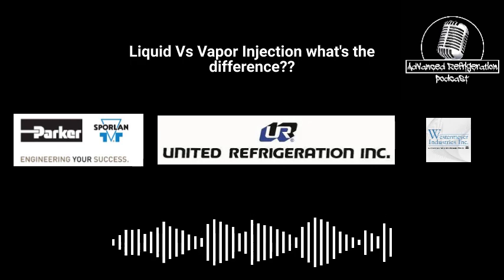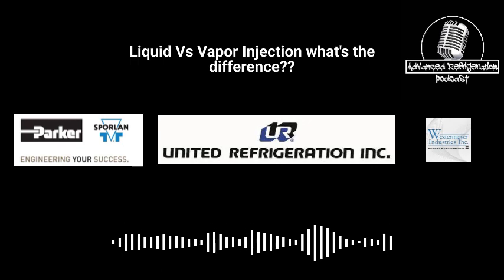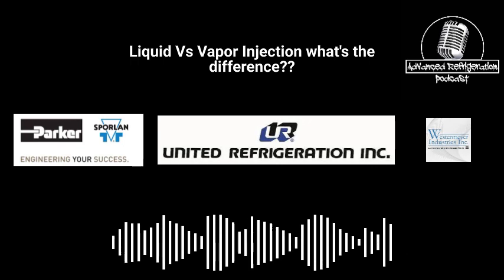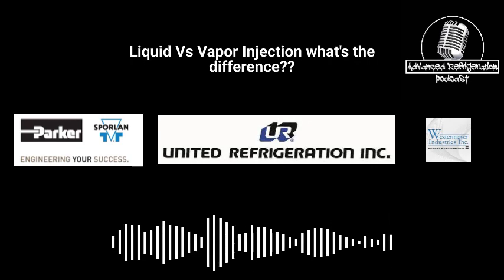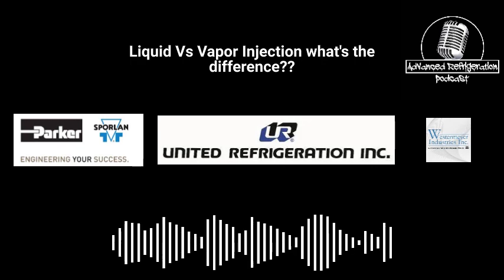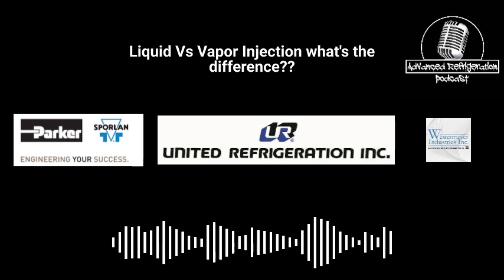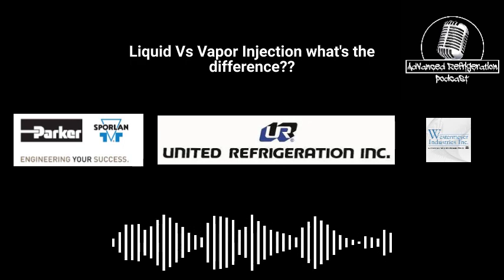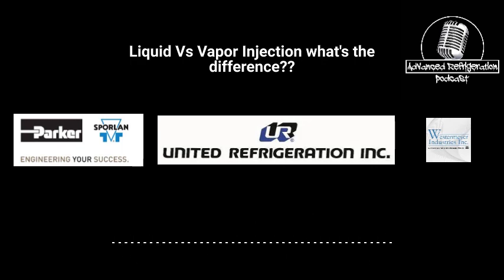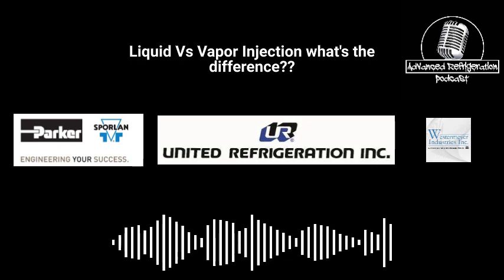Yeah, a telltale sign at the Bullseye stores is a common call. You get a guy going there for an oil failure. It's cooler out, didn't really find much. Then the next guy goes there for an oil failure, and they all start looking at the temp, right? Pretty much you can nail it on the head. The first thing I'm looking for is the discharge temp of the rack. If I see the rack discharge temp is low, below 130 degrees, 120 degrees, especially if it's warm out, you're flooding back down the vapor injection, or you have massive liquid flood back down the suction.